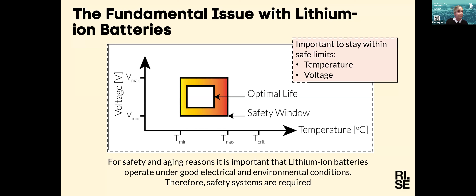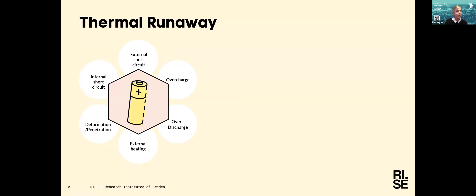So what happens if we don't operate under the right conditions, or if any other error occurs? The cells will enter a state called thermal runaway, which can be triggered by overcharge, over discharge, or external heating, also from deformation or penetration, and from short circuits, both internal or external. What happens in the cell is that the temperature starts rising, triggering exothermic chemical reactions, producing more heat, which triggers even more reactions until the temperature becomes uncontrollable and rises very quickly, and the event becomes very hard to stop.